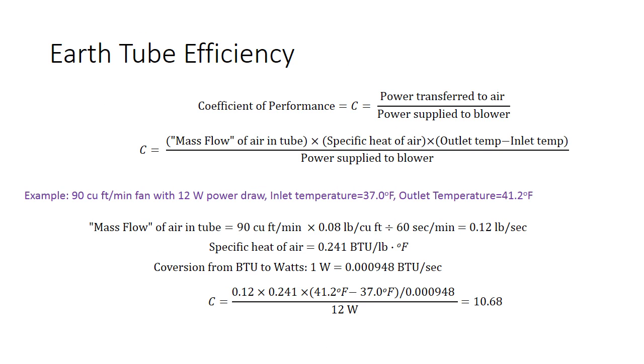Some notes on the efficiency of these earth tubes. This is an equation, not super complicated even though it looks like it. A typical measure of efficiency of any heating or cooling system is called the coefficient of performance. Essentially that's the power transferred to the air via heating or cooling divided by the power supplied to the blower.